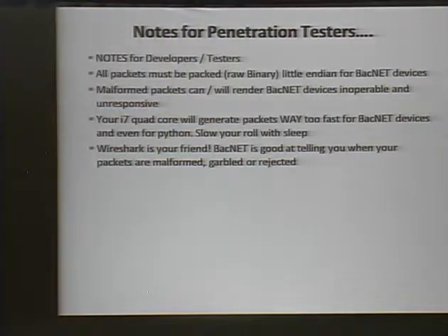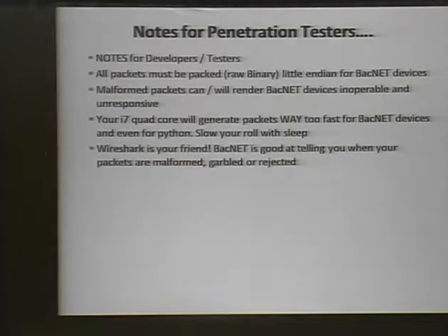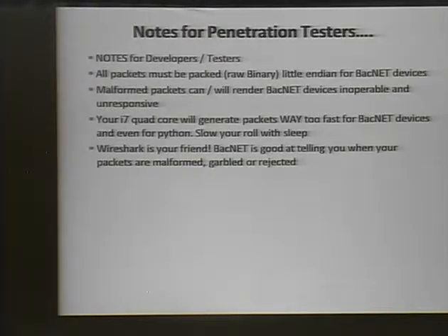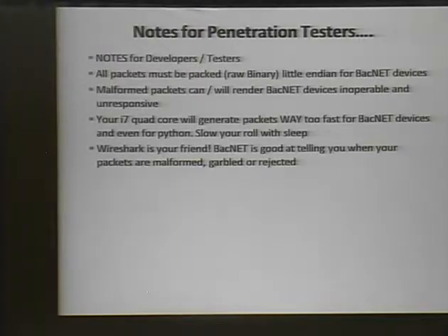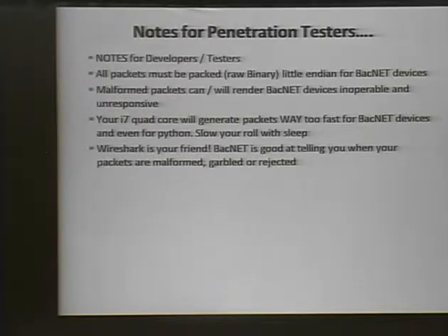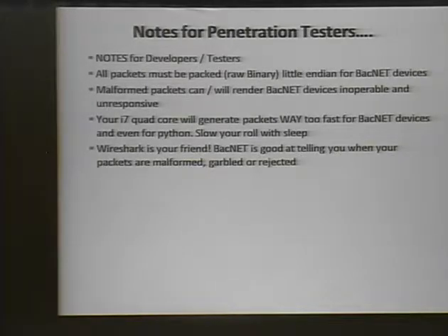A note for pen testers: all packet stuff is packed in raw binary, little-endian format. Malformed packets can and will render some BACnet devices inoperable, so be careful when testing against a building — they can stop responding. Also, your typical modern laptop will crush these devices; they simply can't handle the speed at which a laptop can generate packets. Wireshark does have a plugin to decode BACnet packets.